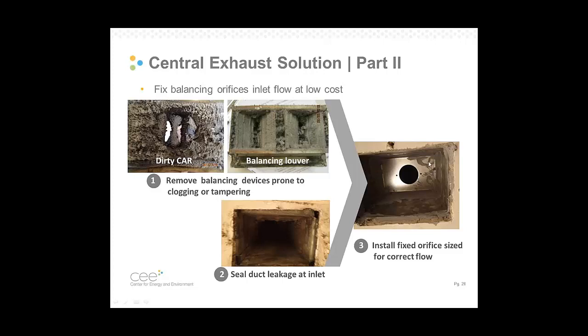So the solution is this picture on the right here. It's basically a piece of sheet metal with a hole in it, and the hole is sized for correct flow at a specific shaft pressure. This is a really simple solution that doesn't clog up over time, and it's much cheaper. It's $5 to $7 versus $30 to $40 for one of these on the left. So this is a great, low cost solution.